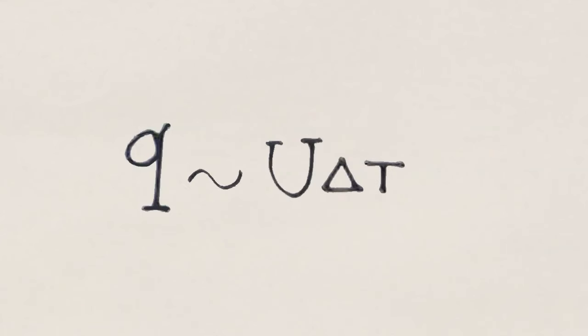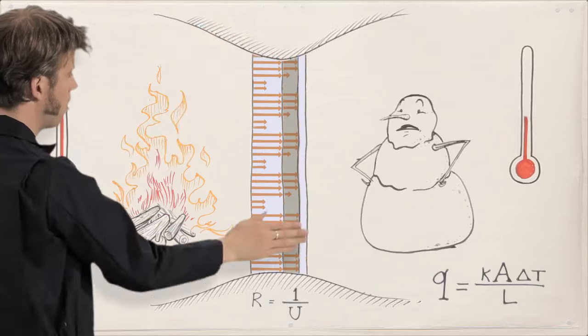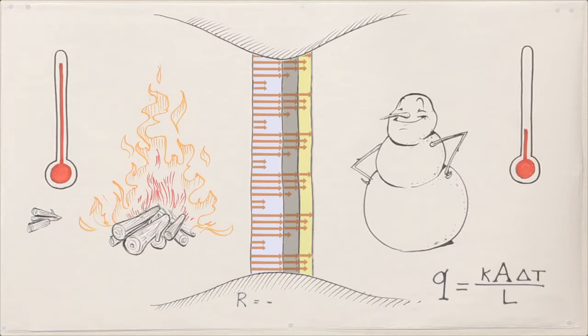But to insulate, you want high thermal resistance. That's the material's R-value, which is 1 over its U-value. Thermal resistance behaves similarly to electrical resistance. Adding layers of materials in series adds their R-values linearly.